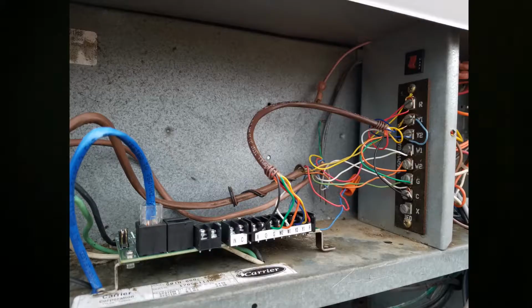To install the thermostat sensor, first turn off power to the HVAC unit. Second, open the service panel and identify a suitable location for the thermostat sensor. After that, you're going to connect each terminal on the HVAC's thermostat board to the corresponding terminal on the thermostat sensor board. Now, if some of your terminals are jumpered, just use one wire. And for those terminals that don't have any wires, simply do not connect them.